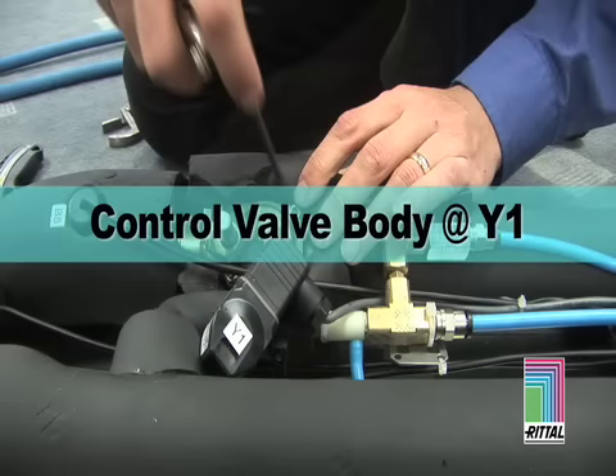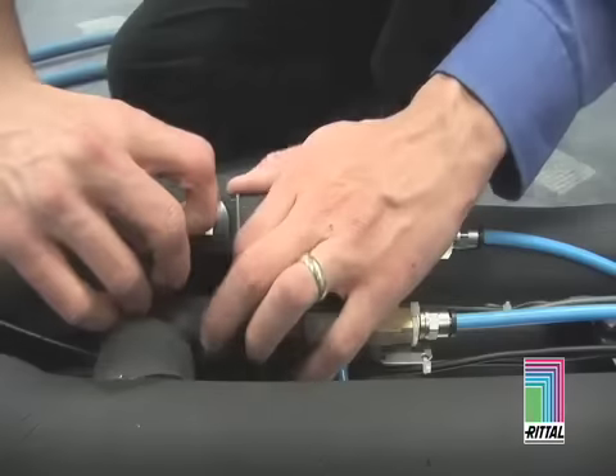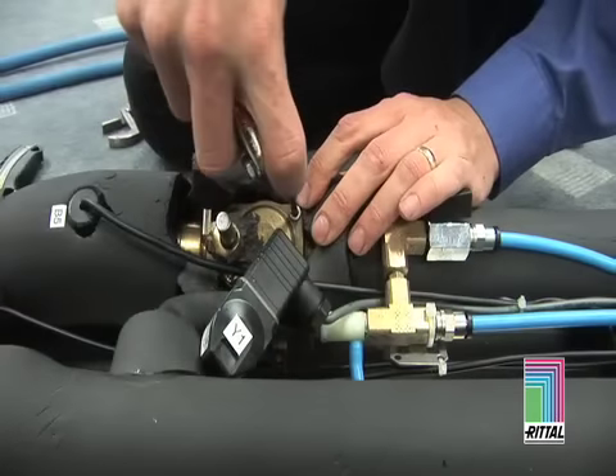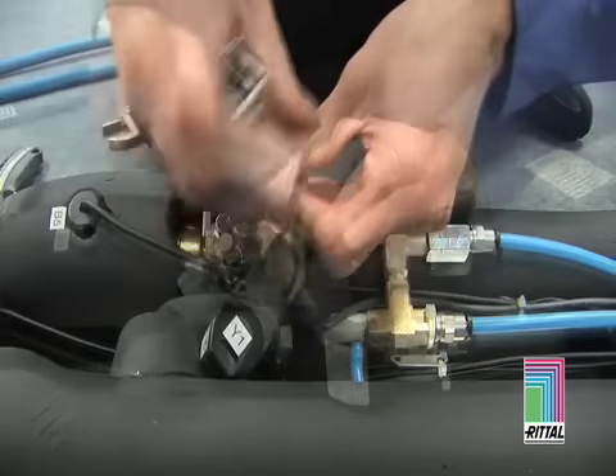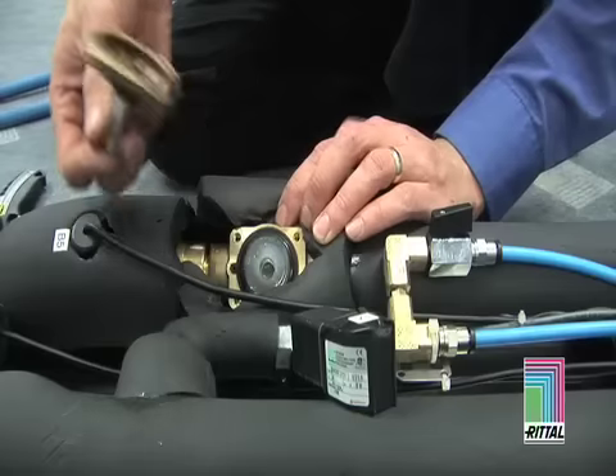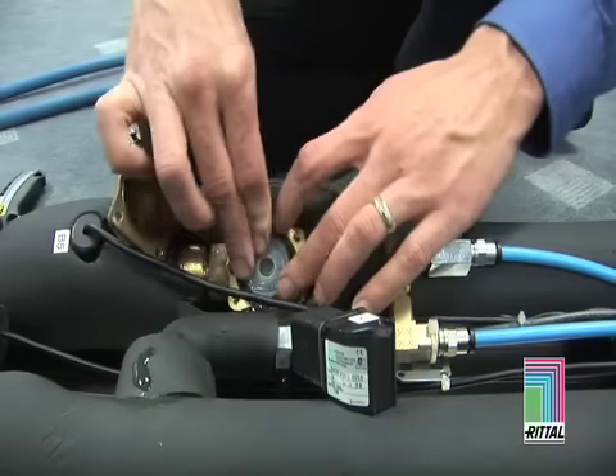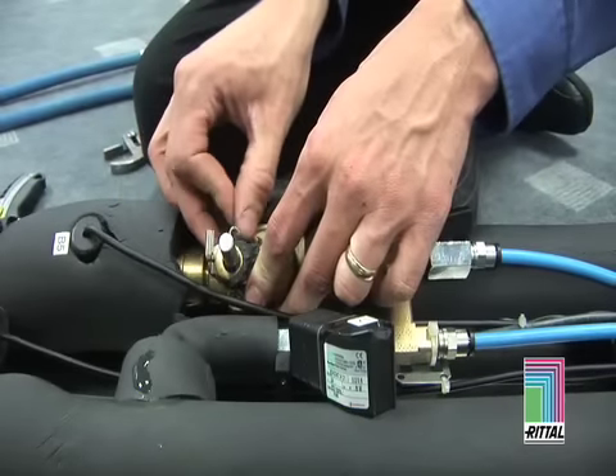Control valve body servicing. Remove the insulation surrounding the control valve. Remove the retaining hex nuts. Remove spring and diaphragm. Replace spring and diaphragm with new parts. Reattach all insulation and re-glue insulation in place.